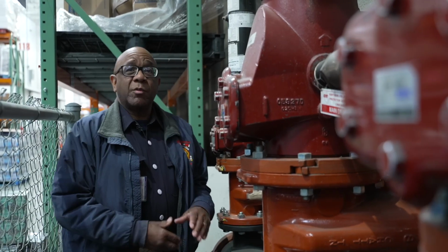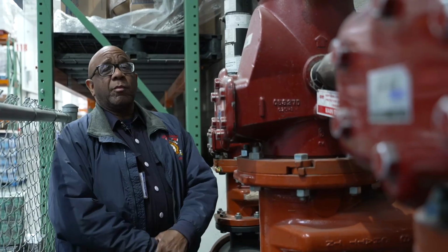All right, today we're going to be continuing to look at our mercantile occupancies. In this case, we're going to look at a manifold fire sprinkler system for a commercial occupancy. We're going to be looking at the calc plates. We're going to look at the spare sprinkler heads. You're going to get an opportunity to see the dry pendants that are used in your freezer and your refrigerated occupancies.